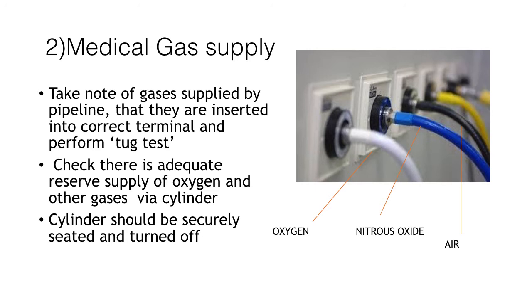The pipelines are connected to the anaesthetic machine via a non-interchangeable screw thread connector. When checking the machine, you should check that the colours match up at the Schrader valve and the pipeline, and you should also perform the tug test — ensuring that when you tug the pipeline, it is securely seated in the Schrader valve at the wall. In addition to the pipeline, you should also check there is an adequate reserve supply of oxygen and other gases available via cylinders on the back of the anaesthetic machine. These spare cylinders should be full, securely seated, and also turned off so they are not leaking.